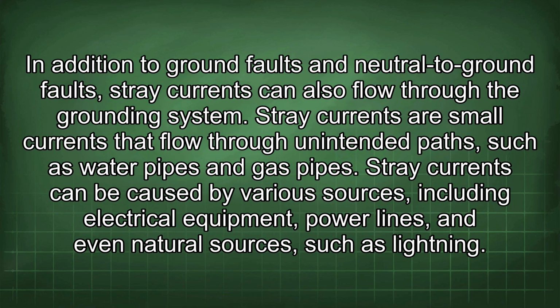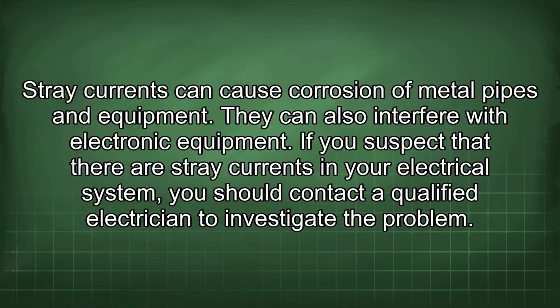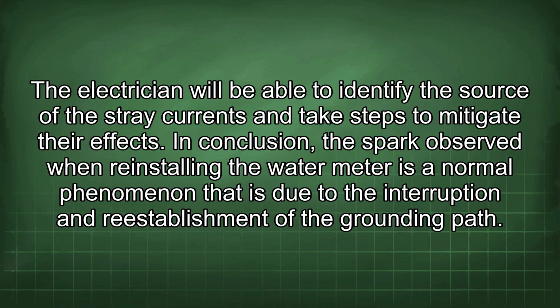In addition to ground faults and neutral to ground faults, stray currents can also flow through the grounding system. Stray currents are small currents that flow through unintended paths, such as water pipes and gas pipes. Stray currents can be caused by various sources, including electrical equipment, power lines, and even natural sources, such as lightning. Stray currents can cause corrosion of metal pipes and equipment. They can also interfere with electronic equipment. If you suspect that there are stray currents in your electrical system, you should contact a qualified electrician to investigate the problem. The electrician will be able to identify the source of the stray currents and take steps to mitigate their effects.